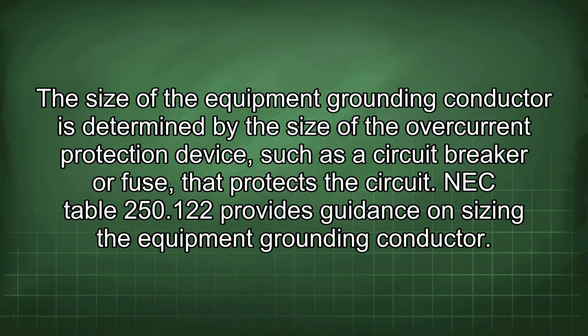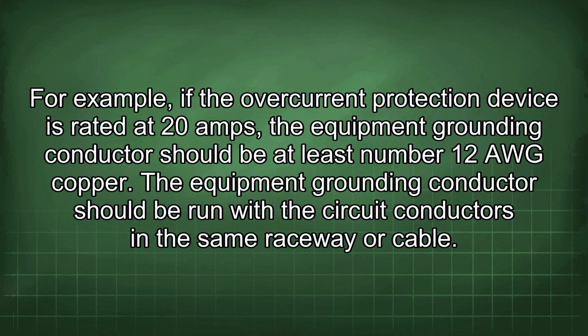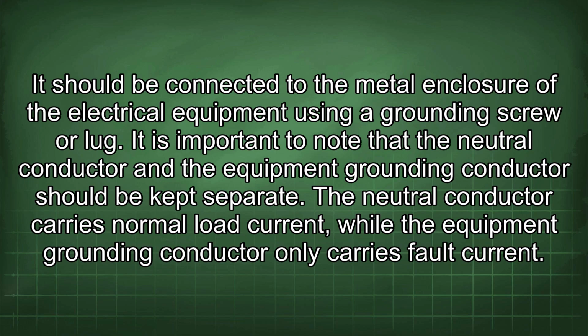The size of the equipment grounding conductor is determined by the size of the overcurrent protection device, such as a circuit breaker or fuse, that protects the circuit. NEC Table 250.122 provides guidance on sizing the equipment grounding conductor. For example, if the overcurrent protection device is rated at 20 amps, the equipment grounding conductor should be at least number 12 AWG copper. The equipment grounding conductor should be run with the circuit conductors in the same raceway or cable. It should be connected to the metal enclosure of the electrical equipment using a grounding screw or lug.